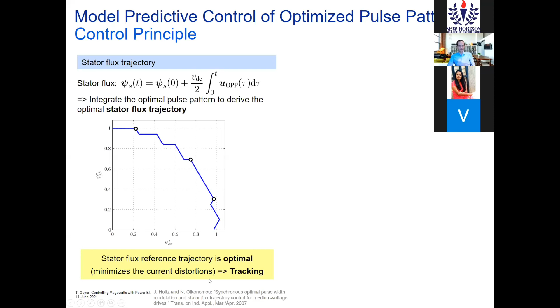How can you follow it? You can change the times when you switch. For example, if phase A has a switching transition from 1 to 0, and the nominal transition would occur at a certain point, delaying it slightly adds a volt-second increment, a correction to the stator flux. By making these modifications in phases A, B, and C, each in their own direction, you can accurately control the stator flux along the desired trajectory.